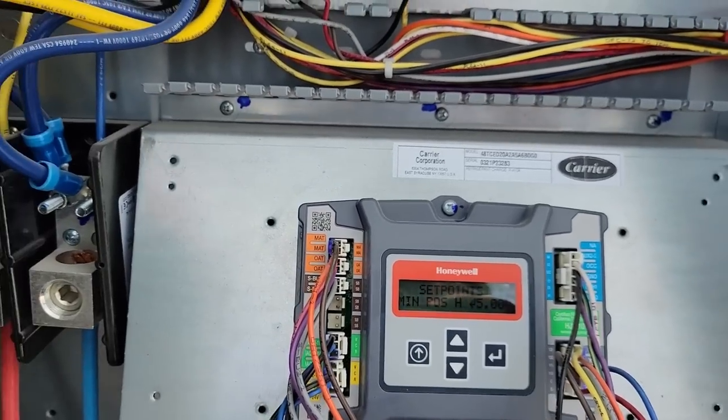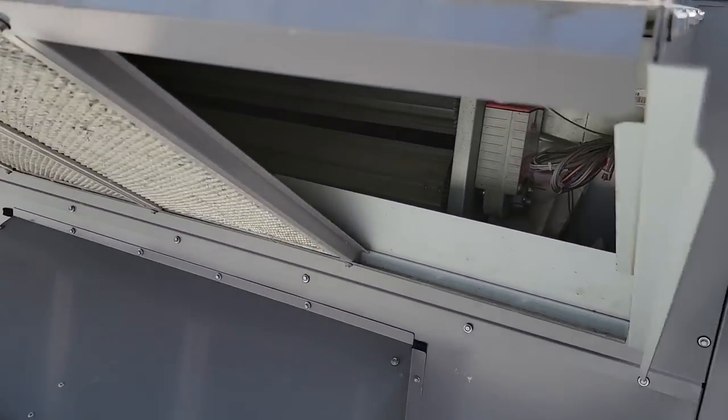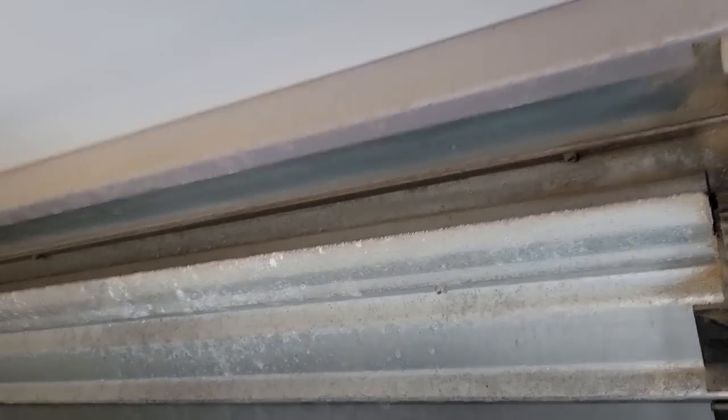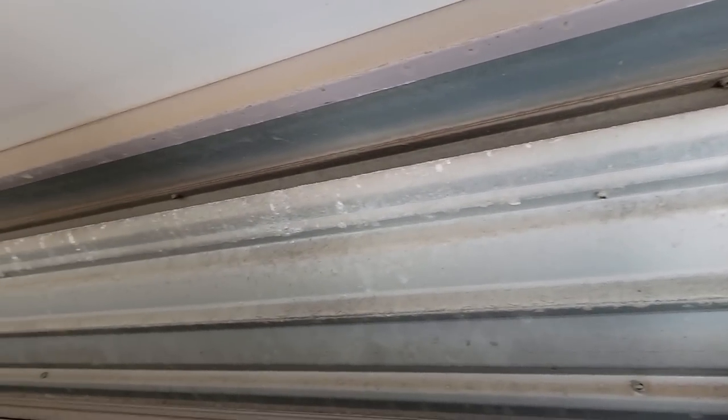Let's go to 5 and see what happens. And then on low, it'll go back open. So that way, when there's not much of a load, it would be less open. But then again, there we go, there's 5 volts. That's maybe a little too closed.